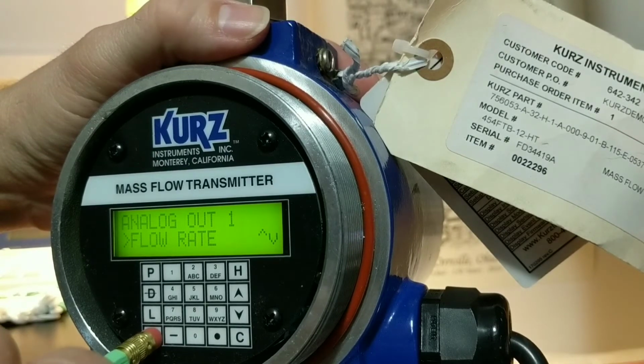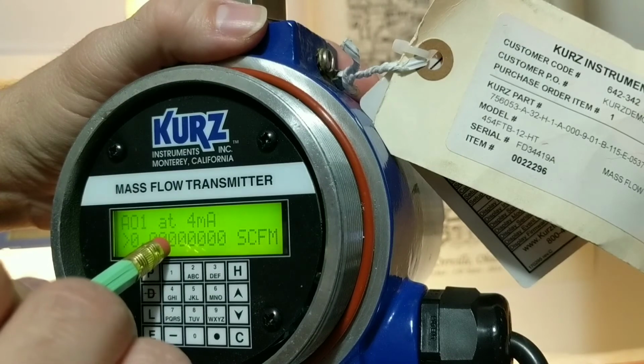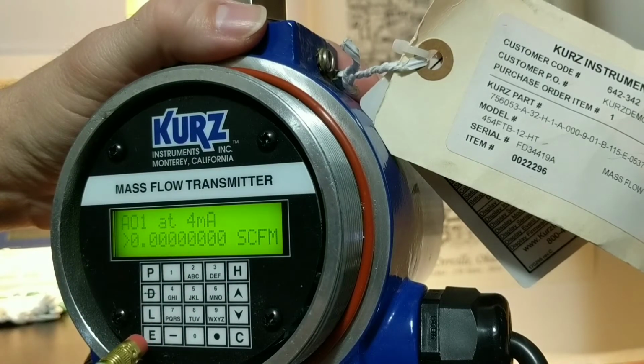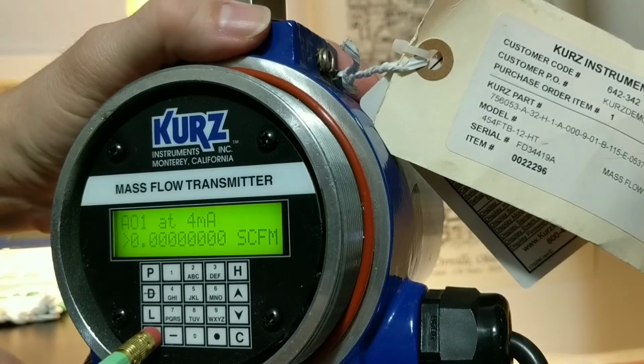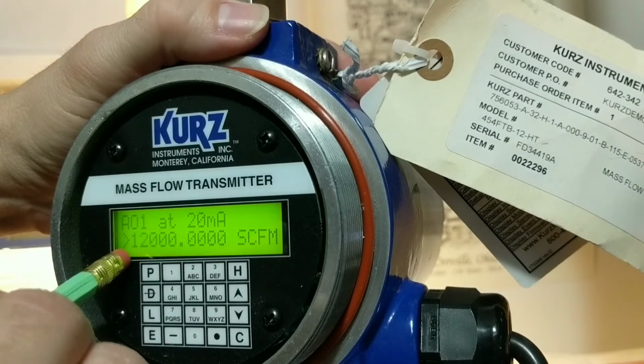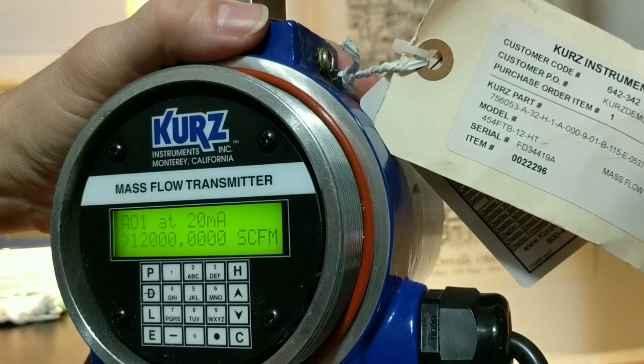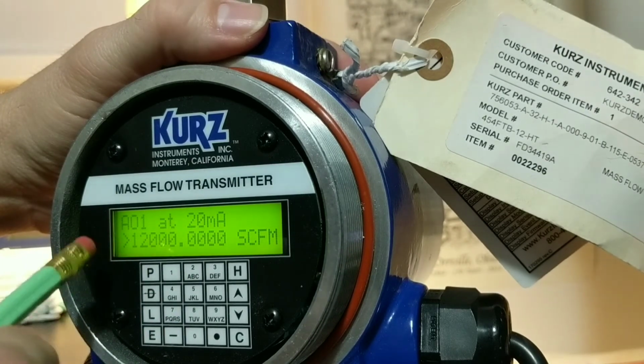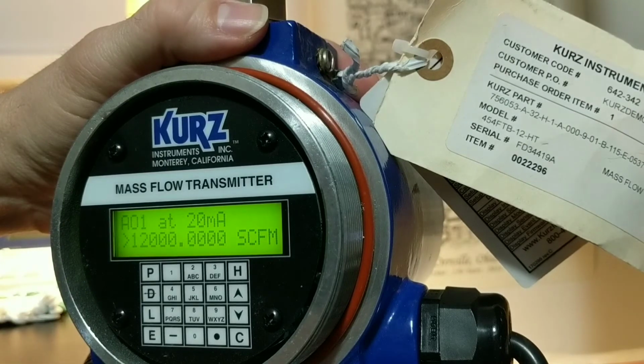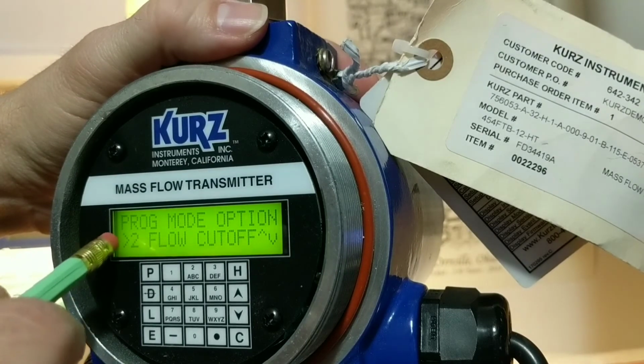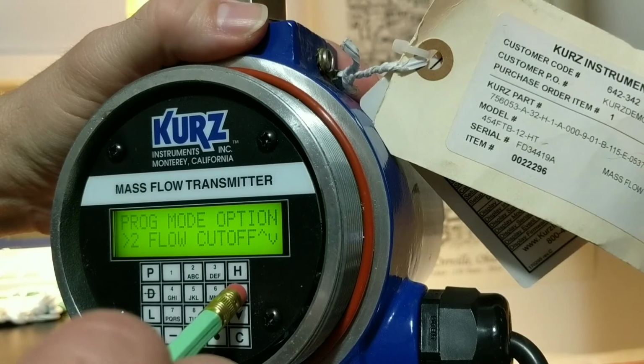And then you can check this, but your analog 4 milliamp is set to 0, which you want to make sure back at the PLC that your 4 milliamp is set to 0 as standard cubic feet per minute. 20 milliamp in this case is set to 12,000. Now you guys could have those set to anything that you want. That's what this one is set to. I'm not telling you to change it to that, but you might want to just jot that down so that you double check that back at the PLC. That stays the same, and we're just going to scroll through the rest of these items, and then it'll jump down until we get on to the next menu item. We're going to skip this one.